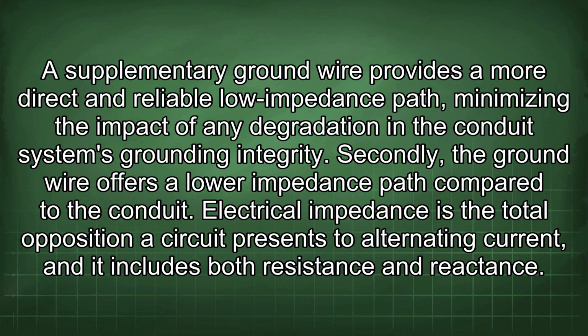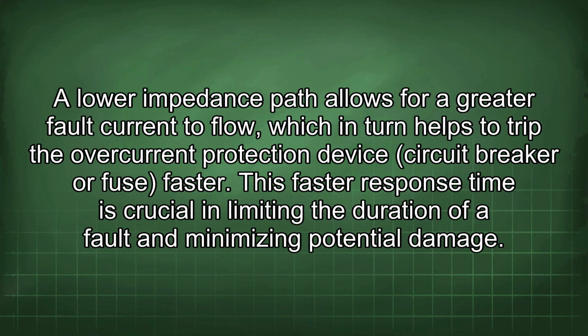Secondly, the ground wire offers a lower impedance path compared to the conduit. Electrical impedance is the total opposition a circuit presents to alternating current, and it includes both resistance and reactance. A lower impedance path allows for a greater fault current to flow, which in turn helps to trip the overcurrent protection device, circuit breaker, or fuse faster. This faster response time is crucial in limiting the duration of a fault and minimizing potential damage.